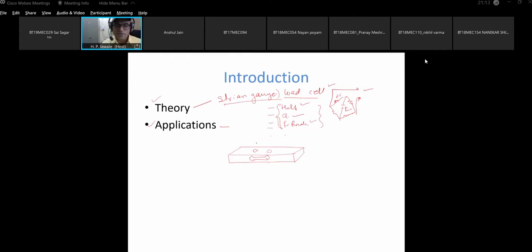And then it will have some strain gauge wires, and those are connected in the bridge circuit. One side is kept fixed, and on the other side we are going to apply load W. Because of load W, it is going to deform, and due to deformation there will be some strains induced which are going to change the resistance of the wire. It is del Rg1, del Rg2, and so on. Right, this is how it functions.